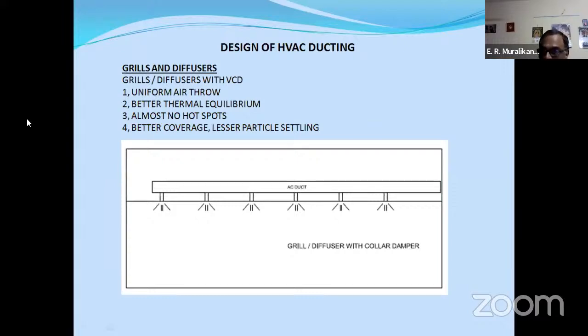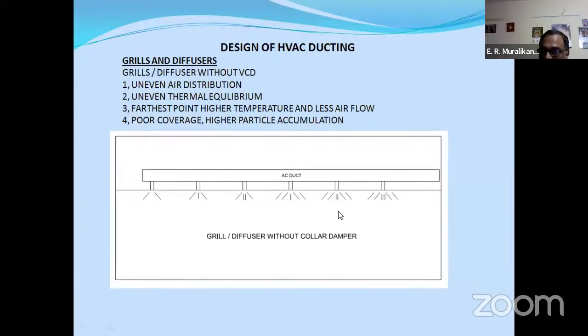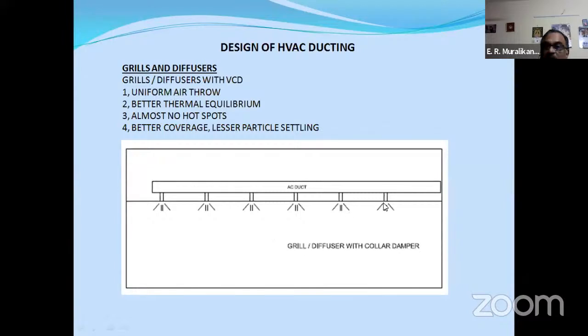With collar damper here. The earlier was without collar damper. It's with collar damper. Next sketch. So you have uniform distribution, almost no hot spots. So in this, air balancing will be very, very easier. You'll have uniform air distribution throughout.